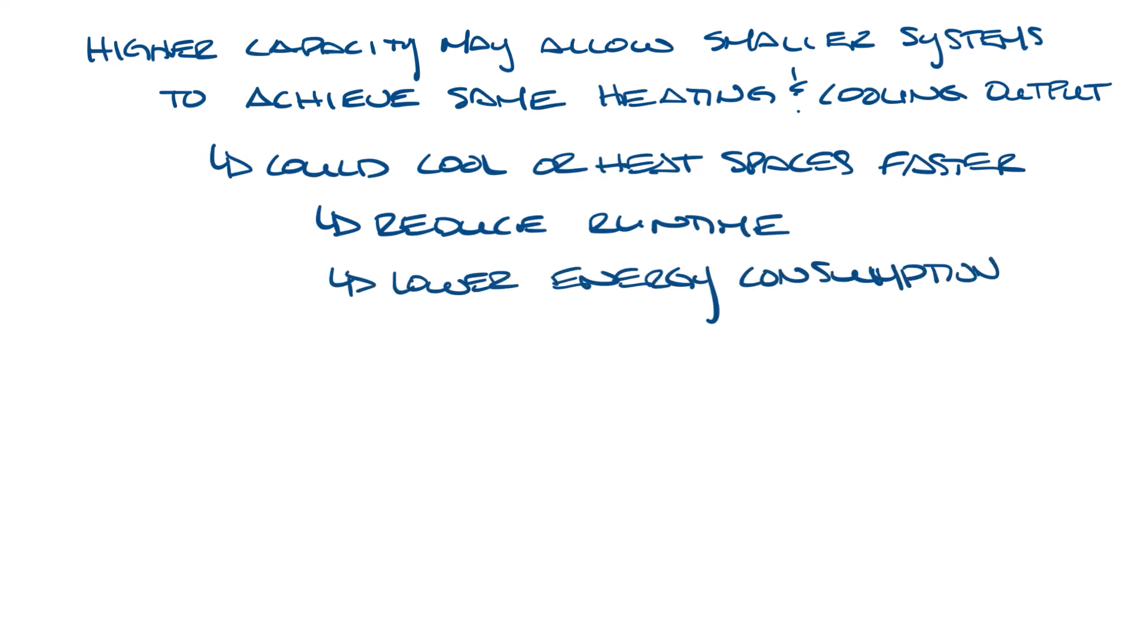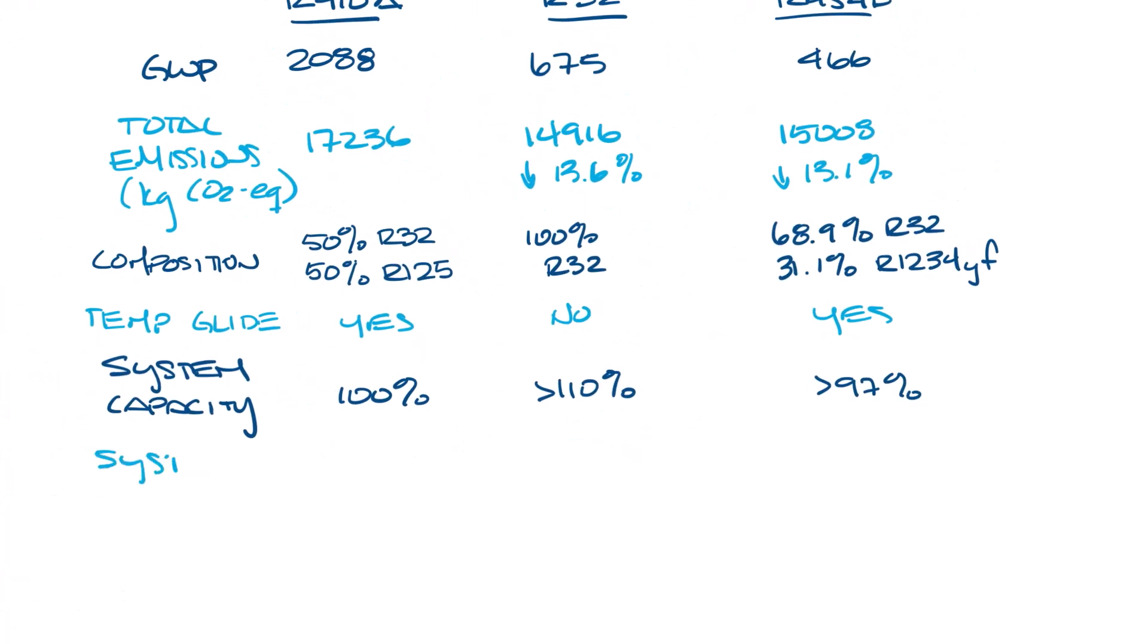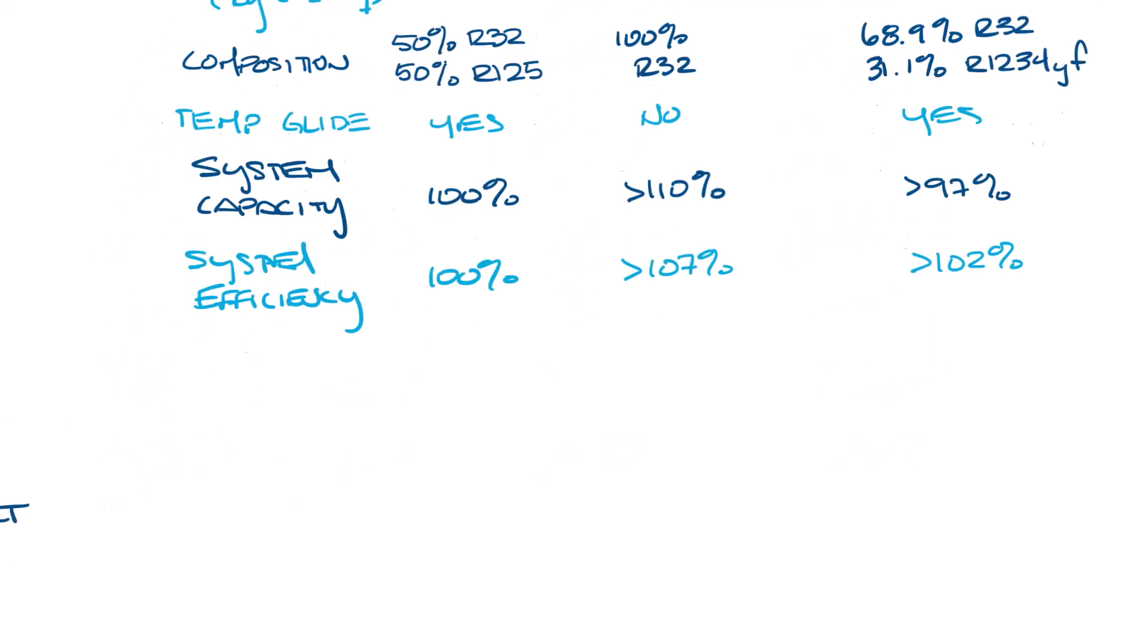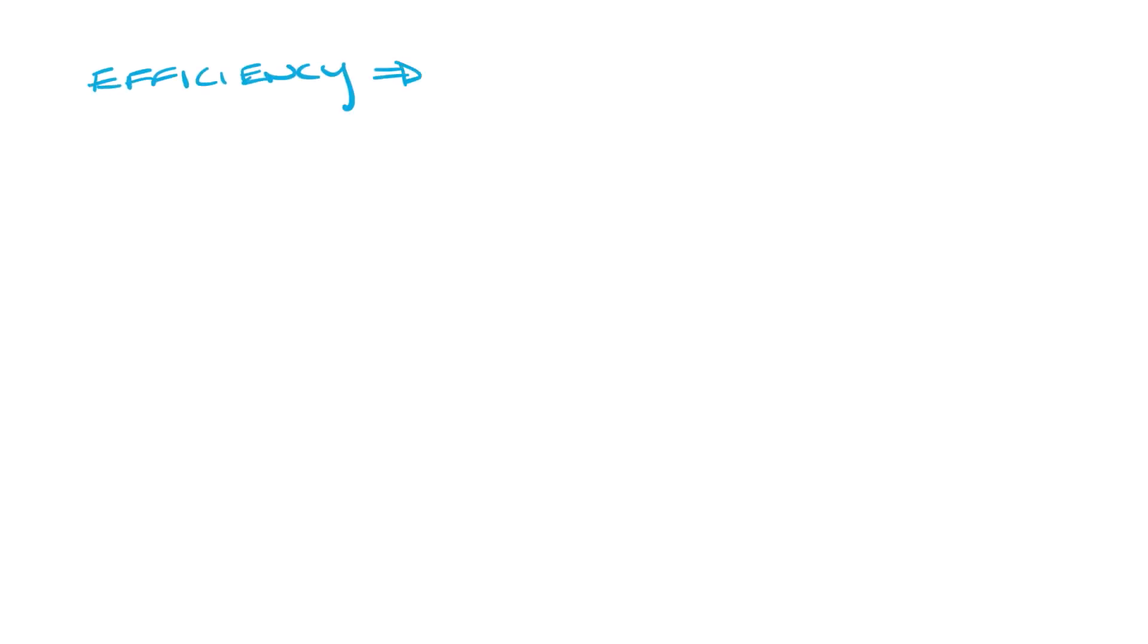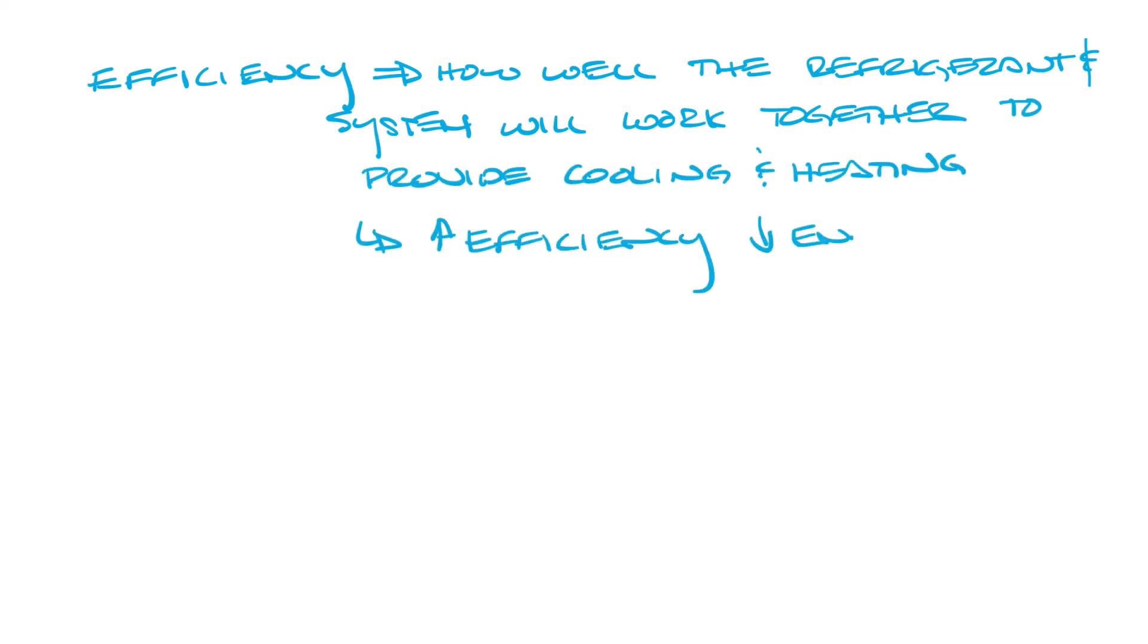Let me move this over a little bit. Go back to our table and look at system efficiency. Again, R410A is baseline, so let's just call that 100%. R32 would be greater than 107% efficiency, and R454B would be greater than 102%. Let's slide over here now. Efficiency basically tells us how well the refrigerant and the system work together to provide cooling or heating. The higher the efficiency, the lower the energy costs.